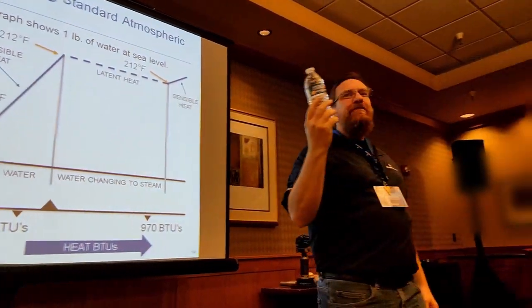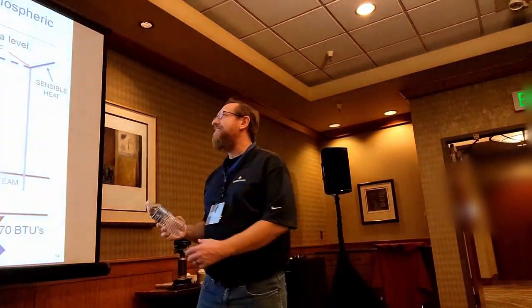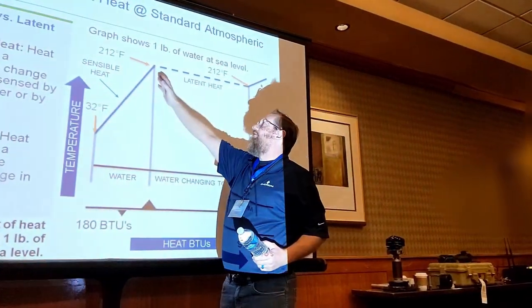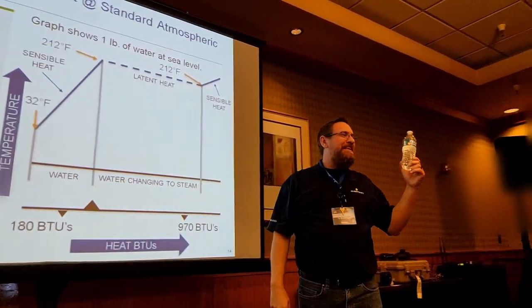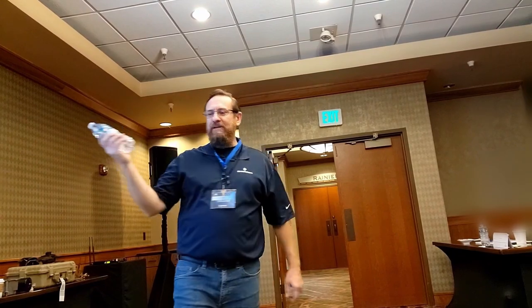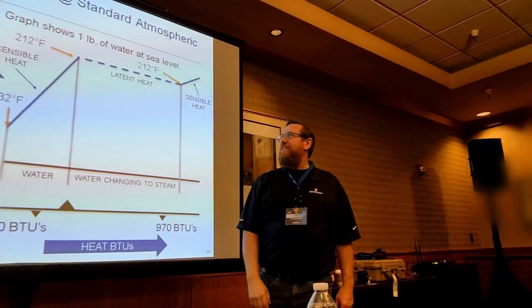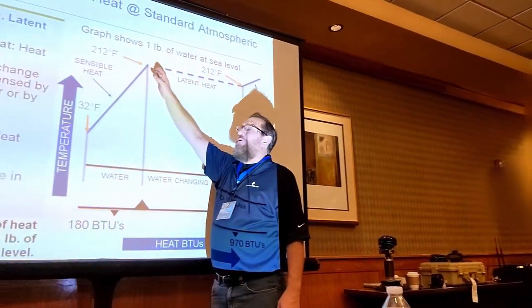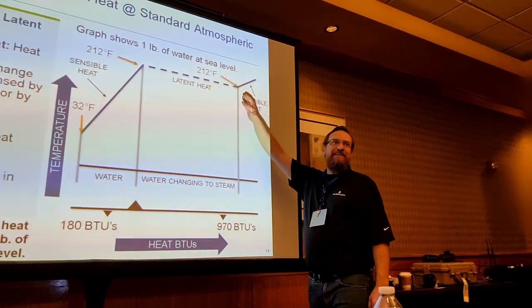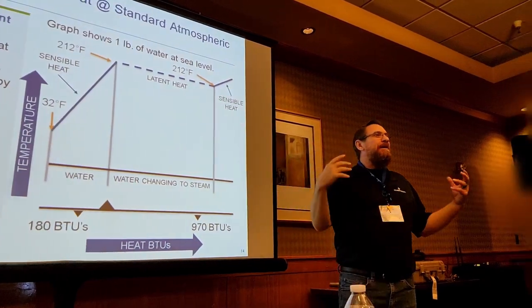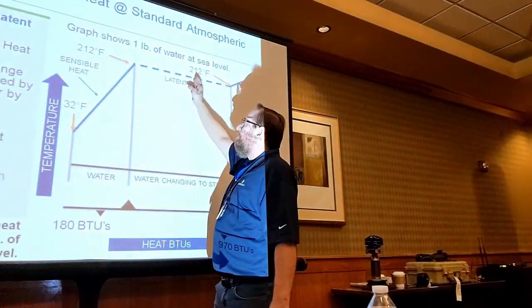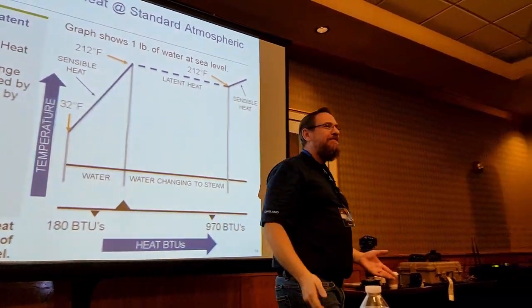All the different refrigerants have different BTU capacities where they absorb different amounts of heat when they're changing states. But that changing state is so important. When we get to that latent heat, that's the magic of refrigeration. That evaporator — that refrigerant — it's boiling from a liquid to a vapor, absorbing a massive amount of heat. And the condenser is changing state from a vapor all the way back to a liquid, rejecting a massive amount of heat.